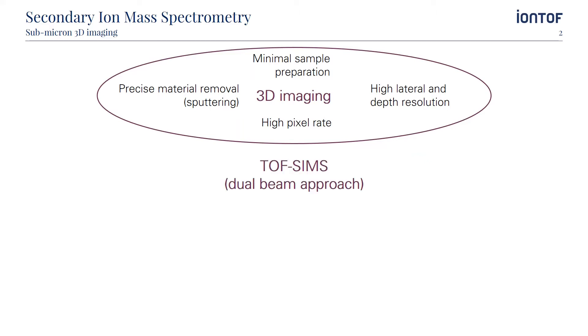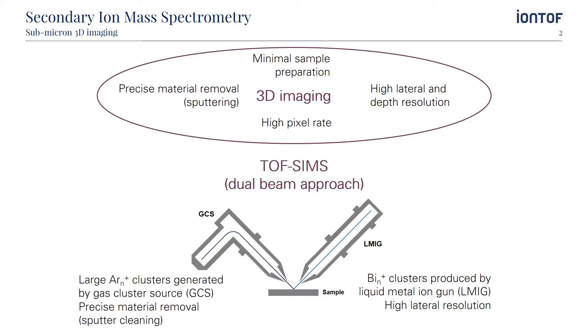Therefore, TOF-SIMS, in particular the dual beam mode, is one of the standard techniques routinely applied for 3D imaging. For organic depth profiling applications, typically two ion beams are employed: a liquid metal ion gun using bismuth clusters as primary ion species for high lateral resolution imaging, and a gas cluster source producing massive gas clusters for precise and soft material removal.